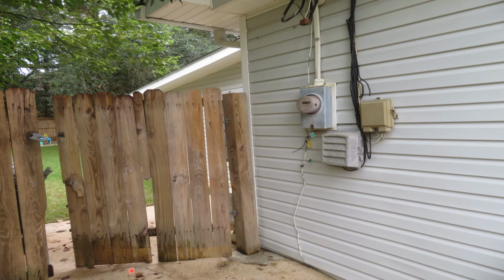In this photograph, what we're looking at is too low a service drop. This was pretty common back in the 60s and probably the early 70s - they would just come in and tie it off right here at the house. But the problem with that now is this is really too low. It should be a minimum of 8 feet, and you're only looking at maybe 6.5 to 7 feet to the bottom of this drip loop.